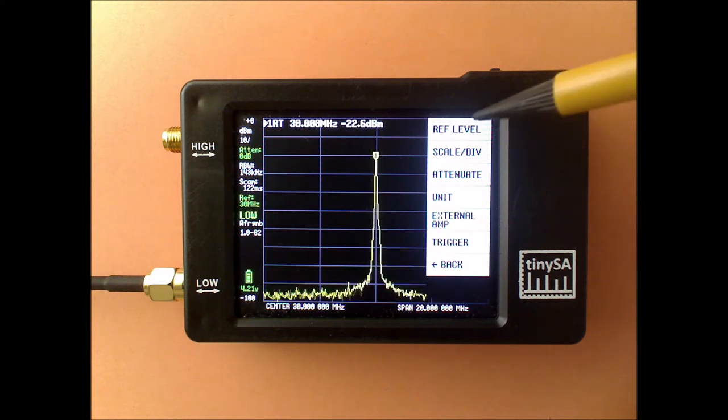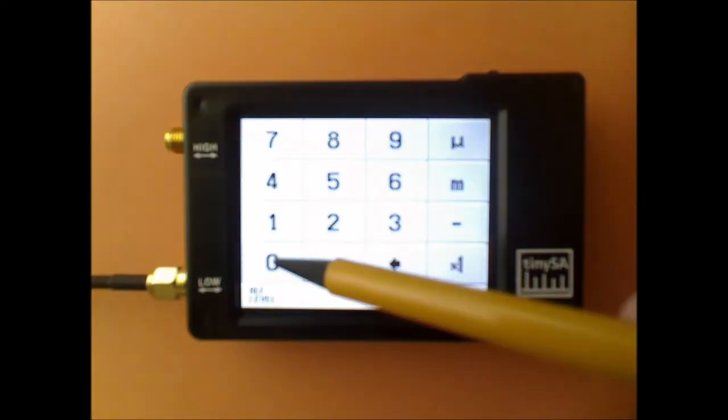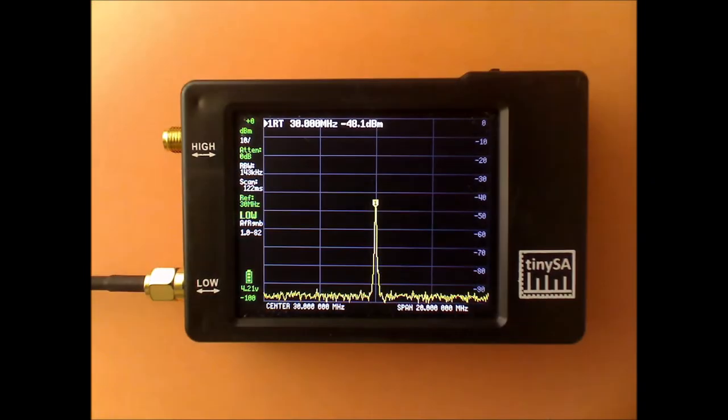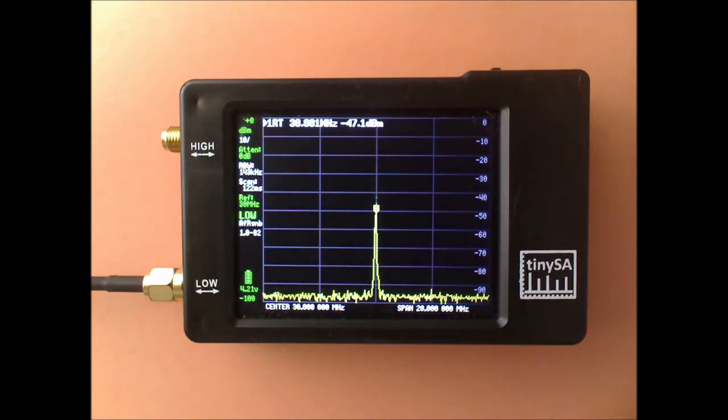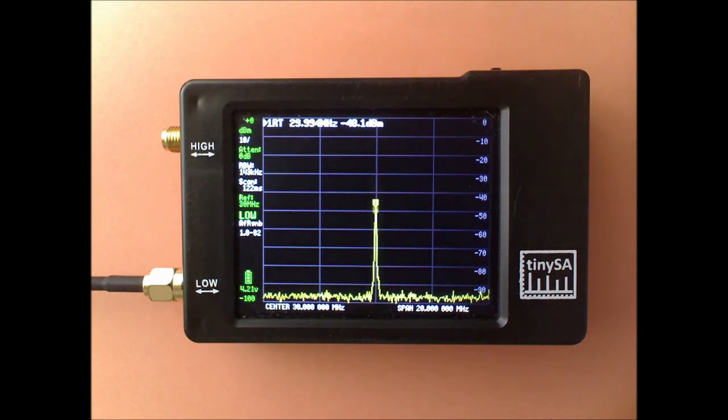In that case it makes sense to set the REF level to a manual level. For instance we set it here to zero and then you can easily see that the signal makes a certain change while the noise stays at the same level.